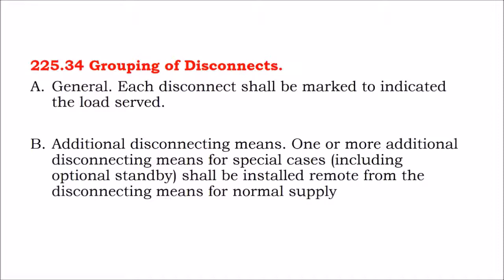Okay, well then there are reasons for additional disconnecting means, and that would be for your emergency backup systems or even your standby systems. And so here's the problem. Let's say the fire department shows up and they want to power down the building before they go inside. They should not have to flick more than 6 switches to de-energize the building. And so they get there and they flick all the switches. Well, what if one of those switches powers the respirators? And so by flicking that switch, the hospital loses its emergency backup power, and all of a sudden their patients undergo cardiac arrest or whatever.